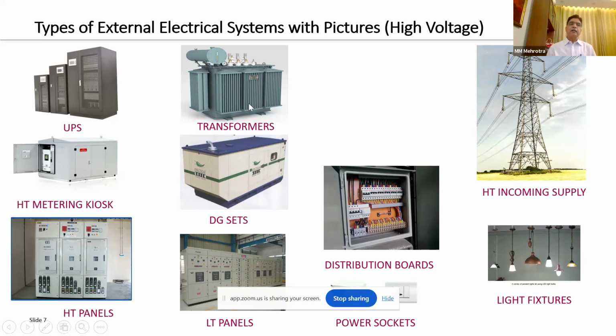Now HT supply is coming to my transformer. What will happen? The transformer will reduce the voltage to LT. First, HT supply is coming from SEB to my HT circuit breaker. Here, what you see in the figure is the HT panel only. It's a control panel of that HT circuit breaker. The circuit breaker is outside in the yard next to the transformer. The circuit breaker is not here. So if you see this panel, there is no 11 kV or 33 kV supply here. You can consider it's an LT thing.